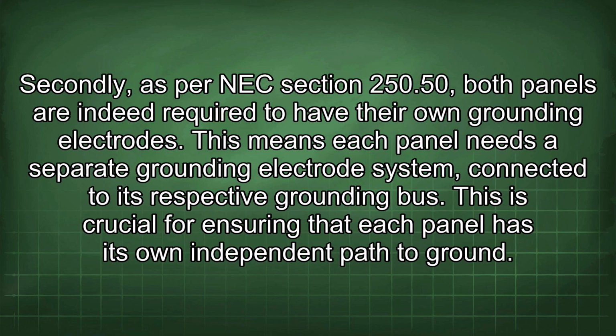Secondly, as per NEC section 250.50, both panels are indeed required to have their own grounding electrodes. This means each panel needs a separate grounding electrode system connected to its respective grounding bus. This is crucial for ensuring that each panel has its own independent path to ground.